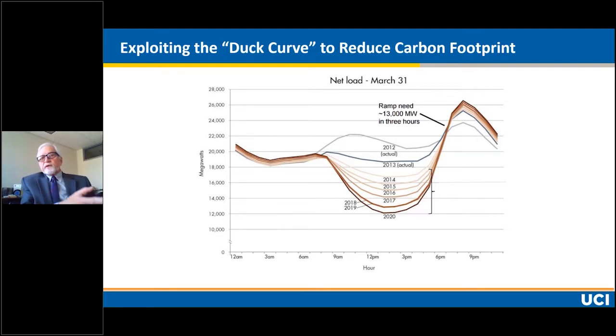So the idea is to take a big thermal storage tank like the one I just showed you, and maybe a second one for hot water, in a campus that has a lot of chillers - they'll have to add some chillers and some heat pumps - and charge those tanks only at the middle of the duck curve, or anytime you can add load, because adding load in the bottom of the duck curve uncurtails renewable power that's otherwise curtailed. It will all be green power. The first CSU campus that does this will become more than 50% carbon neutral on day one. This concept really holds a lot of potential.